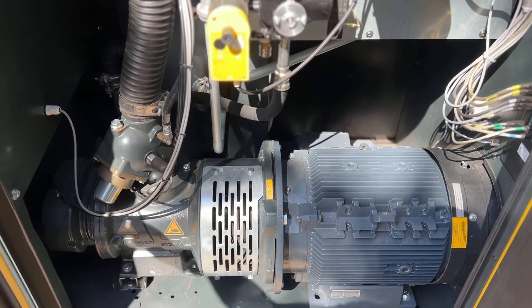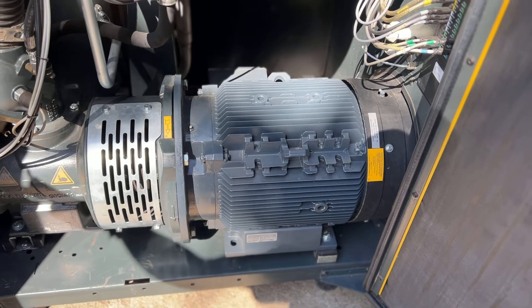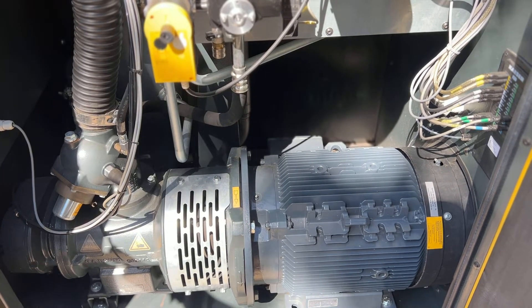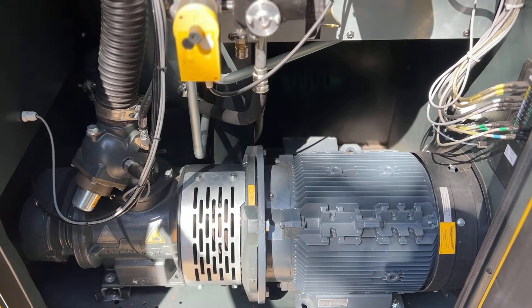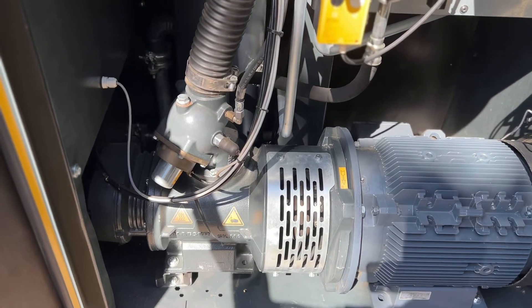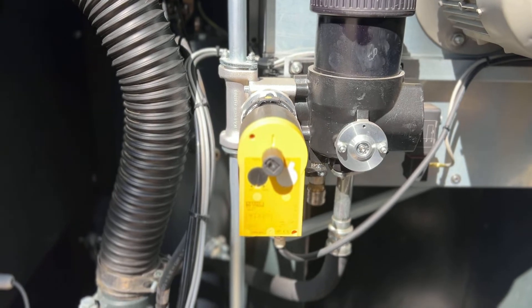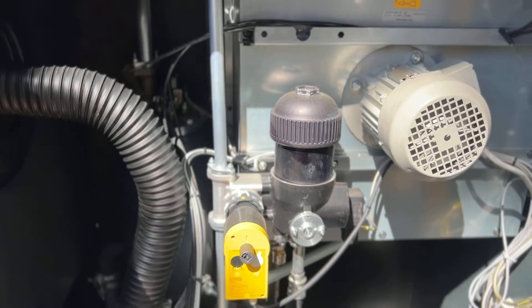It's a direct drive machine. This motor is rated at 27 kilowatts for inverter input, and the compressor is maxed to 8.5 bars, but on eight bars it consumes around 20 amps of power only. We have a Sigma 19 screw element and also a thermostatic actuator right here — you can modulate the temperature as needed.